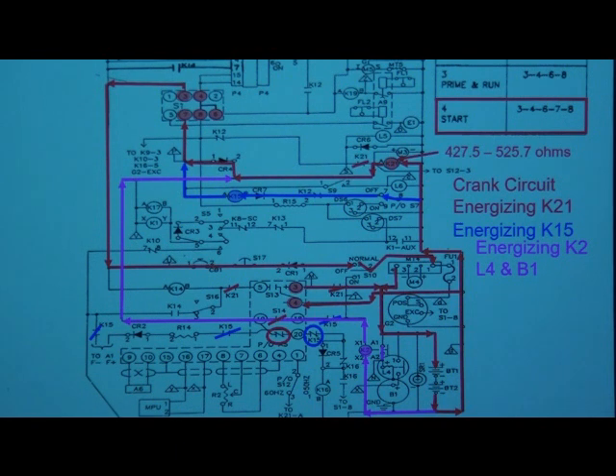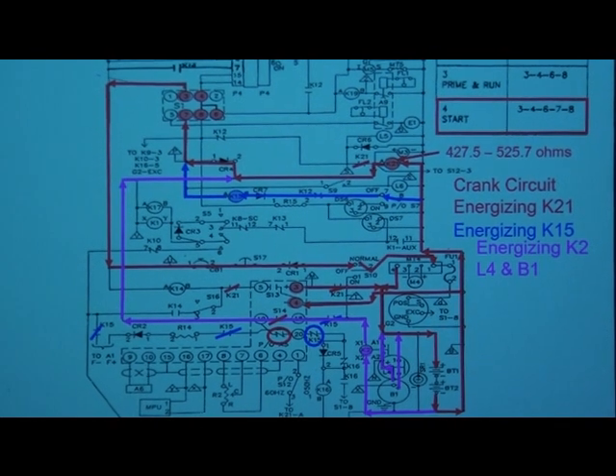The last step we need to do in the crank circuit is to energize the L4 starter solenoid and the B1 starter motor. Our L4 goes through the K2 crank relay contact towards the positive side of the battery. Once there internally, it closes its contacts which allows the B1 starter motor to energize. At this point, our generator is now cranking.